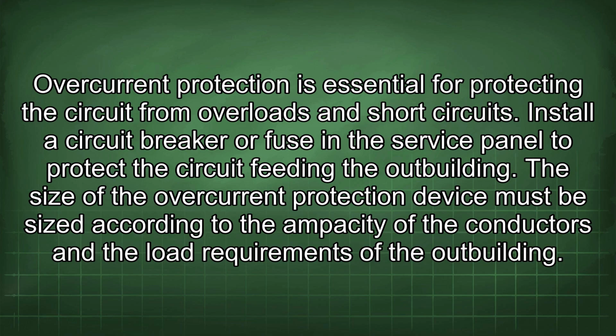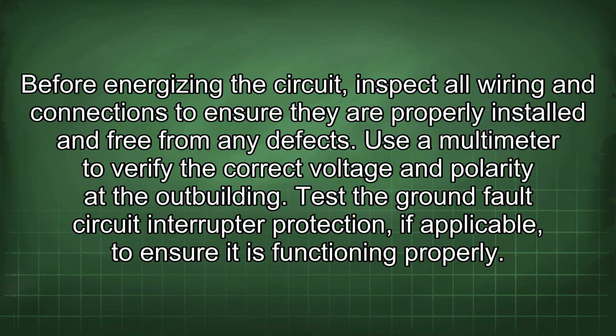Install a circuit breaker or fuse in the service panel to protect the circuit feeding the outbuilding. The size of the overcurrent protection device must be sized according to the ampacity of the conductors and the load requirements of the outbuilding. Before energizing the circuit, inspect all wiring and connections to ensure they are properly installed and free from any defects. Use a multimeter to verify the correct voltage and polarity at the outbuilding. Test the ground fault circuit interrupter protection, if applicable, to ensure it is functioning properly.